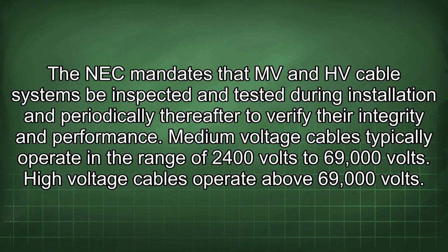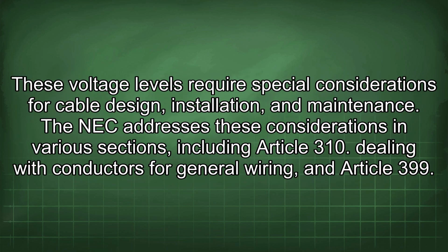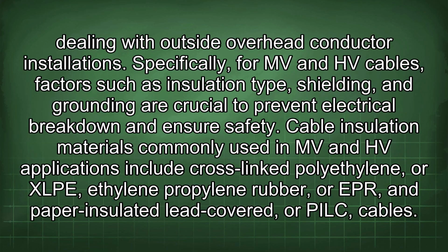Medium voltage cables typically operate in the range of 2400 volts to 69,000 volts. High voltage cables operate above 69,000 volts. These voltage levels require special considerations for cable design, installation, and maintenance. The NEC addresses these considerations in various sections, including Article 310, dealing with conductors for general wiring, and Article 399, dealing with outside overhead conductor installations. Specifically, for MV and HV cables, factors such as insulation type, shielding, and grounding are crucial to prevent electrical breakdown and ensure safety.